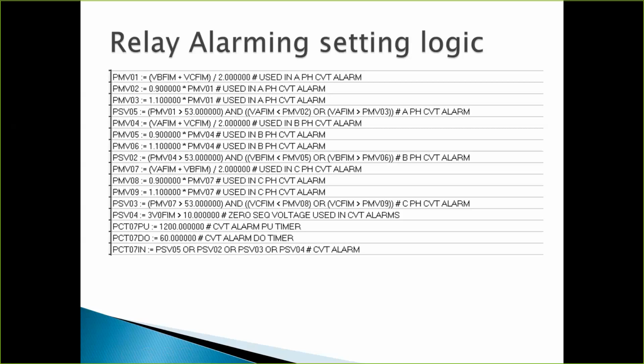So that value is tied with an AND gate, okay, and it's compared to A phase. Remember, I took B phase, C phase, I averaged them out, okay. I've got a variable that's 10% above, 10% below. Is this average greater than 53 volts? If it is, it fires an AND gate, and I compare that AND gate with A phase fundamental magnitude of the other variables, okay? And that is an alarm. If it hits that OR gate, that is the alarm. I do the same thing for A to C, compare it to B, A to B, compare it to C, okay? Does that make sense? I know that it's hard to follow, and I despise these logic settings, but that's what it is.